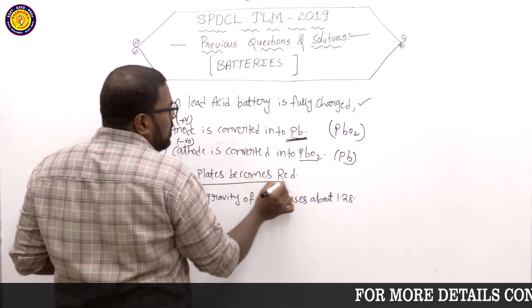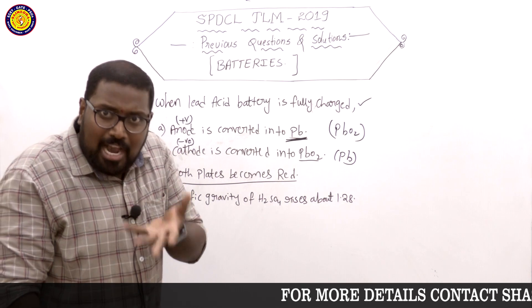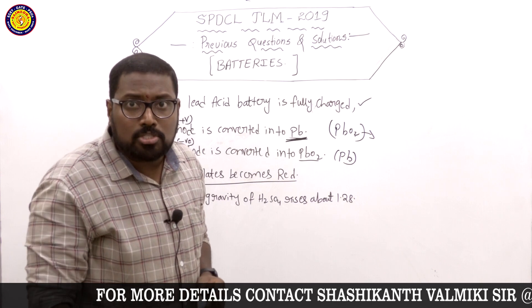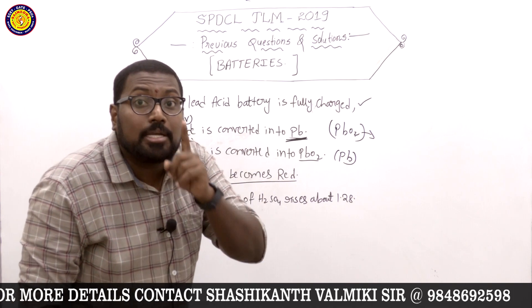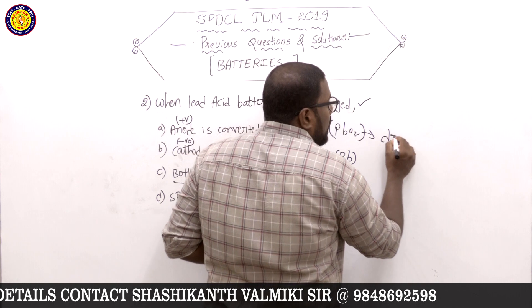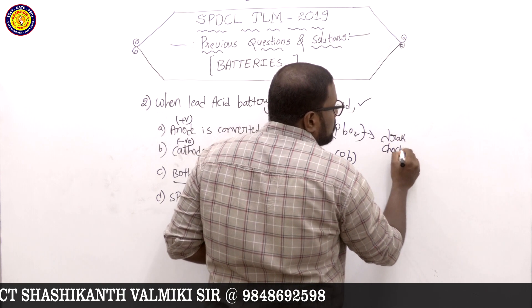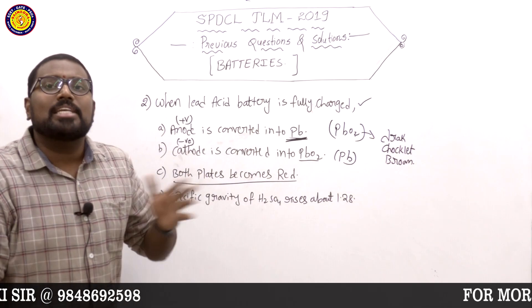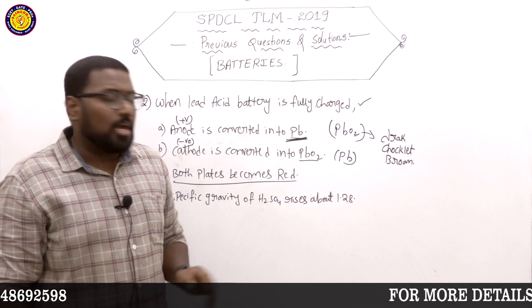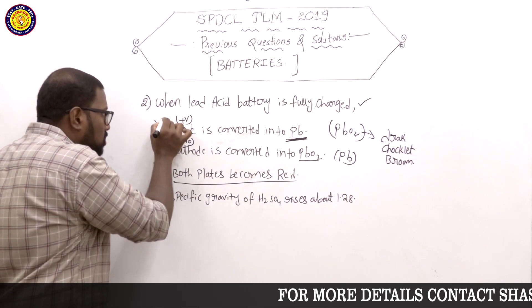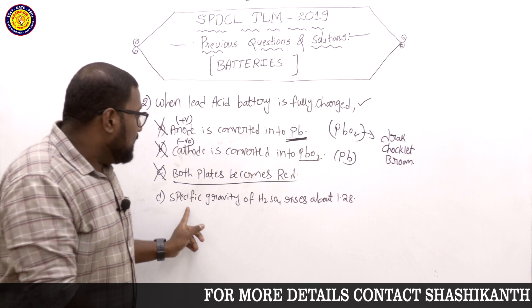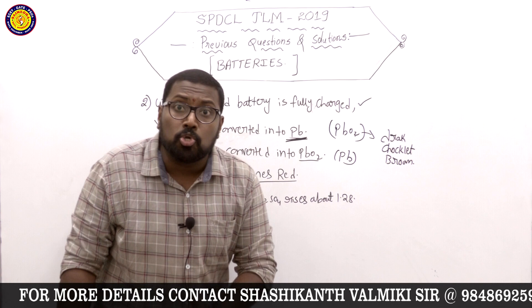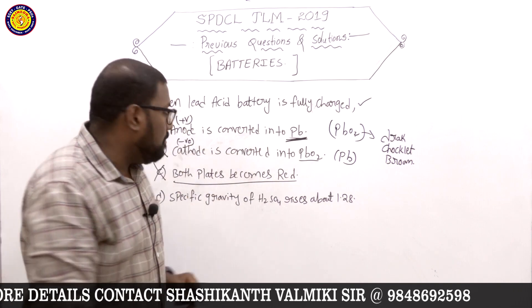Third option: both plates become red — that is not correct. PbO2 is dark chocolate brown in color, not red. So that option is wrong. The correct answer is: specific gravity of H2SO4 rises to about 1.28. This is a very, very important answer.